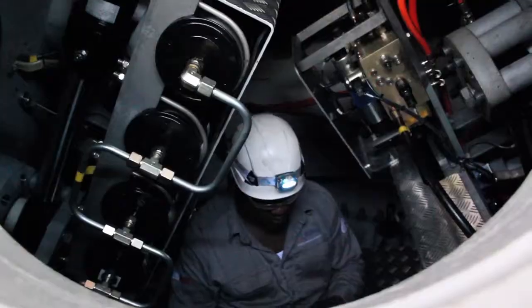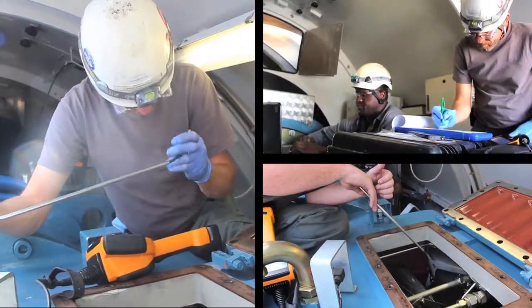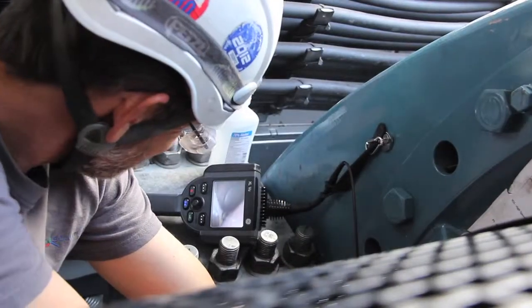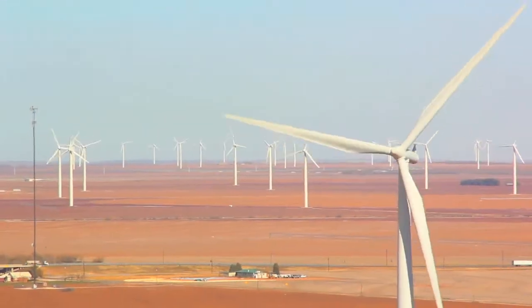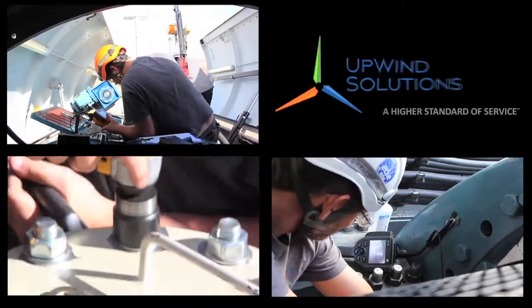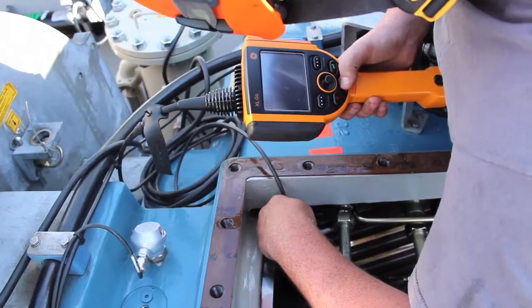Collecting oil samples from the gearboxes months ahead of when the visual end-of-warranty inspection is performed can help you identify wear and degradation in individual units, but we really recommend that wind turbine owners inspect every single gearbox in their fleet, regardless of what the oil sampling result says. The cost of performing a gearbox replacement is so high that it by far outweighs the cost of inspecting every single gearbox on a wind farm of this size and type of turbine.